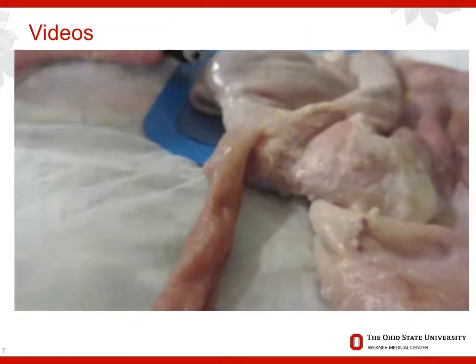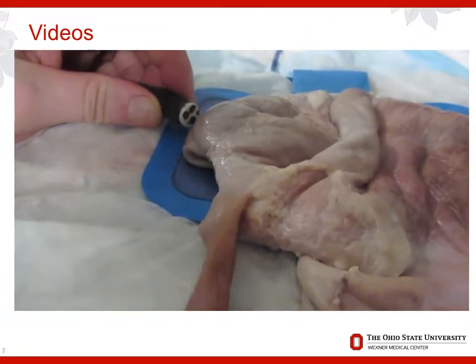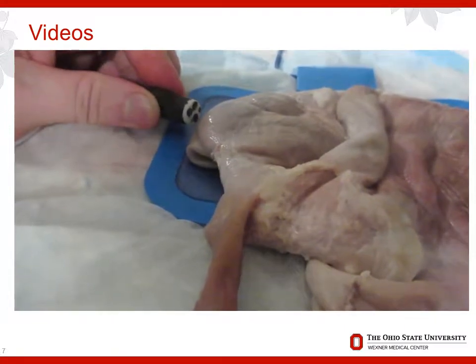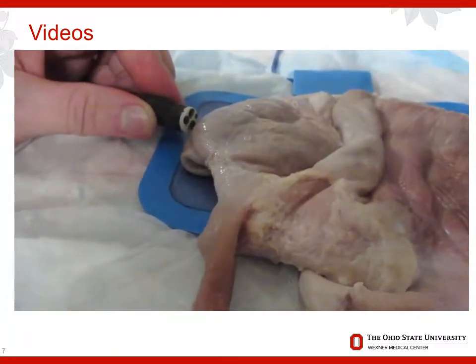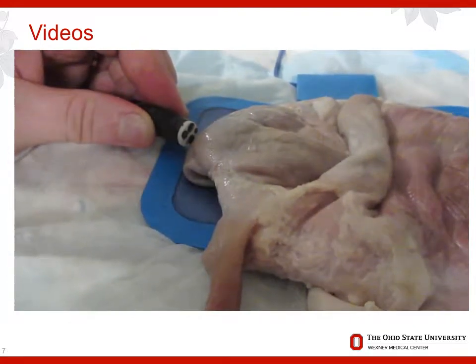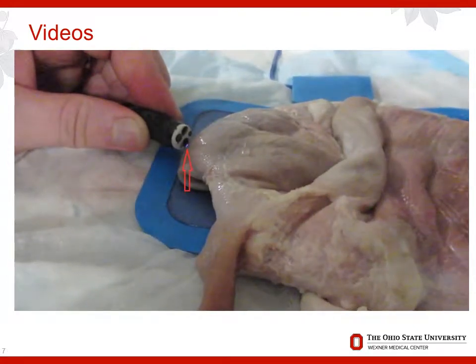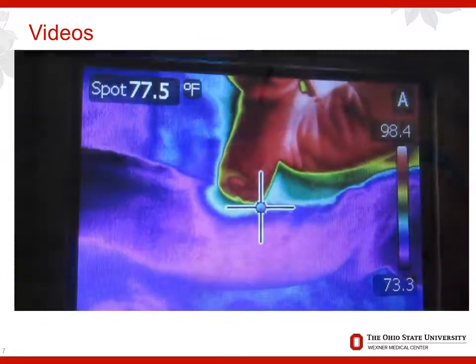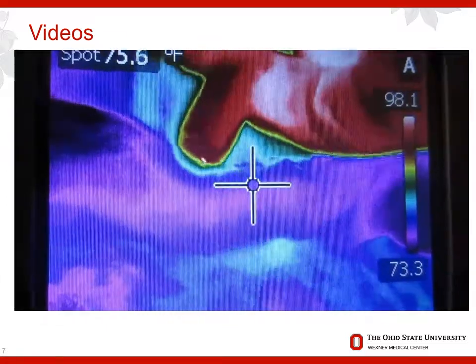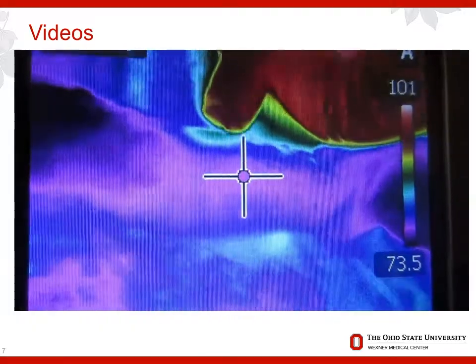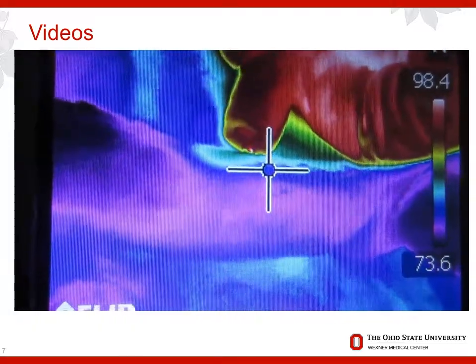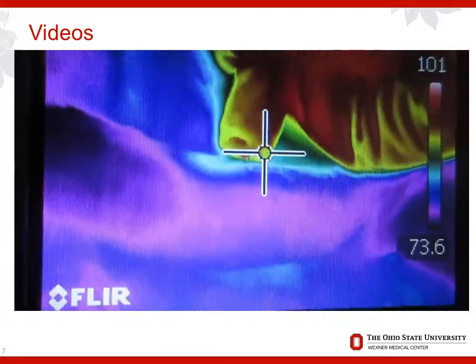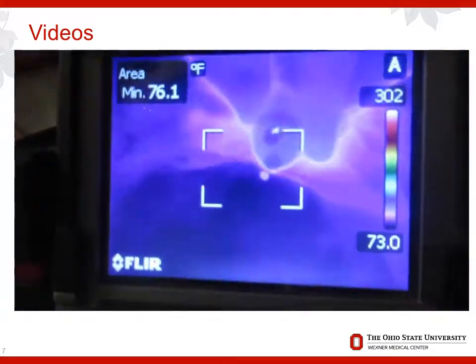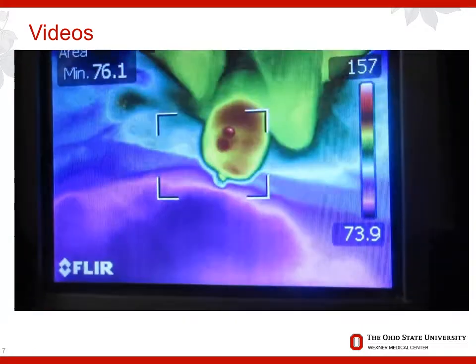To prove this concept, we used a therapeutic endoscope and a standard endoscopic snare that was connected to a generator on baseline coagulation settings. The snare has been retracted into the working channel to maximize our visualization. As expected, we again encountered arcing of energy directly from the endoscopic camera lens to the tissue. These findings were confirmed with a FLIR thermal camera. The white color depicts temperatures near or greater than 100 degrees Fahrenheit. On repeated testing, we noted temperatures as high as 300 degrees Fahrenheit.